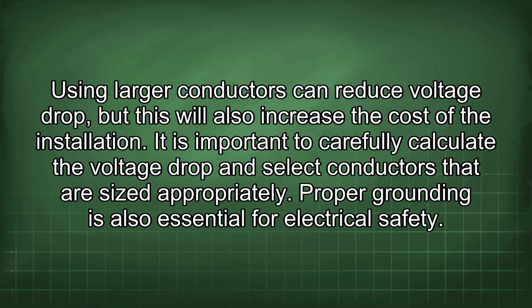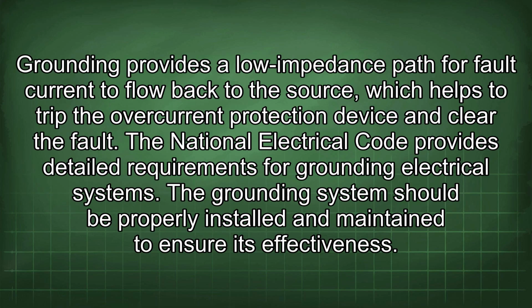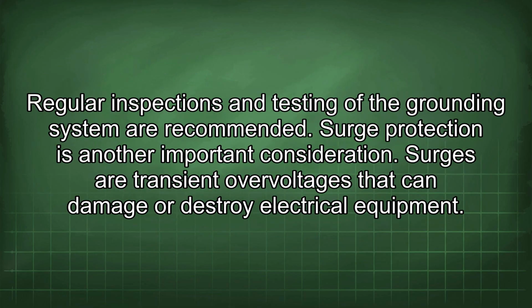Proper grounding is also essential for electrical safety. Grounding provides a low impedance path for fault current to flow back to the source, which helps to trip the overcurrent protection device and clear the fault. The National Electrical Code provides detailed requirements for grounding electrical systems. The grounding system should be properly installed and maintained to ensure its effectiveness. Regular inspections and testing of the grounding system are recommended.